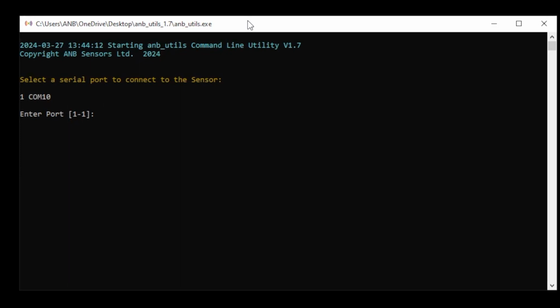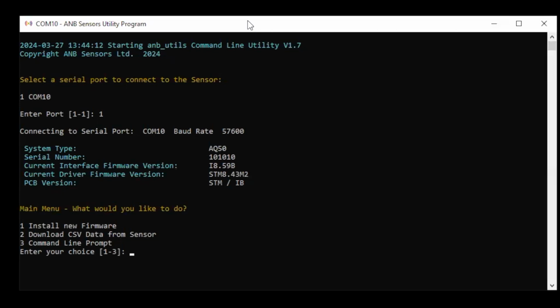To put the sensor into Modbus mode, we first connect the sensor through ANB Utils, turning the sensor on, waiting for the second beep, selecting the COM port, and displaying the sensor information, making note of the baud rate for when we test it in ModScan later. We're going to choose option 3.